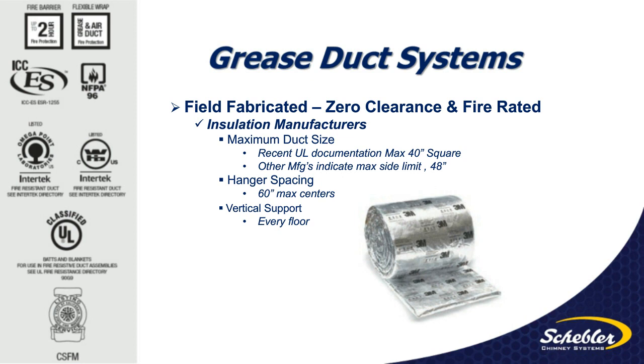Insulation manufacturers have paid and conduct several tests to certify that their insulation is going to be suitable for use for grease duct. So if you look on the left-hand side there, they'll publish that they've done testing through Intertek Labs, UL, testing per the ASTM standard. But in their information, and it might be different based on which manufacturer's information you reference, there is some reference to maximum duct size. A recent document I pulled up the other day indicated that a 40-inch square inner surface area of the ductwork would be the maximum acceptable with their fire wrap on the procedure they gave. Some other manufacturers indicate a maximum side limit of 48 inches. I believe the same square inch internal was the limit, but you could go with the max limit of a 48-inch diameter on one side.